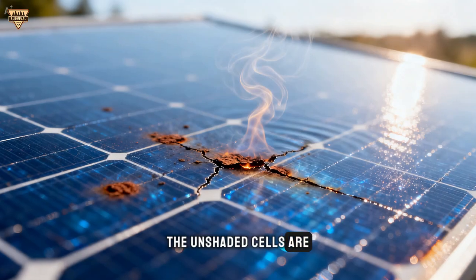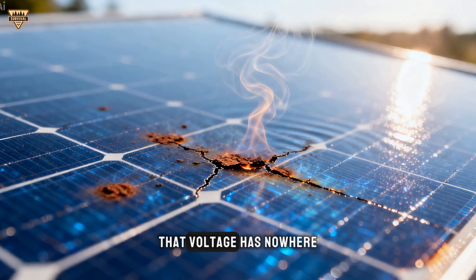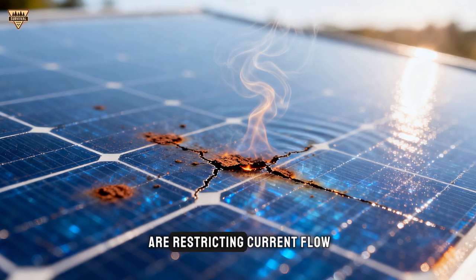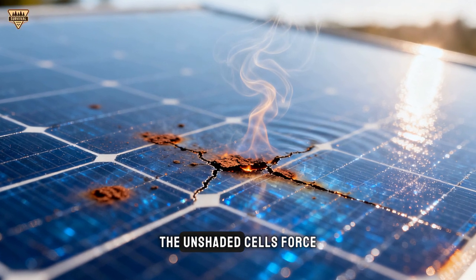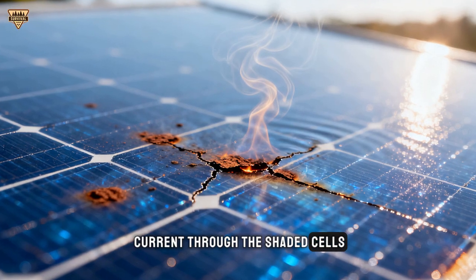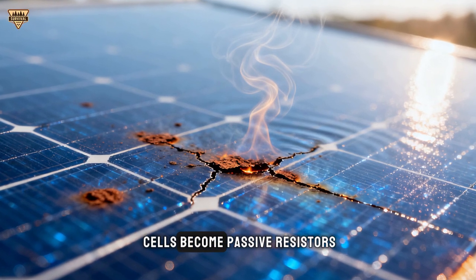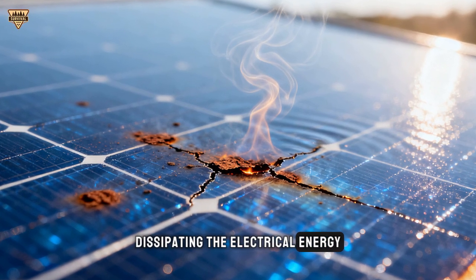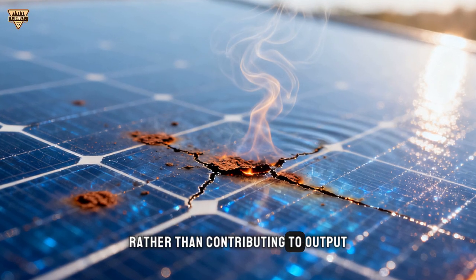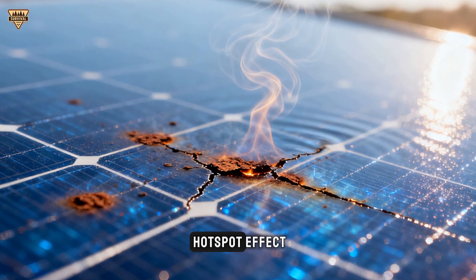The unshaded cells are still generating voltage. That voltage has nowhere to go because the shaded cells are restricting current flow. The unshaded cells force current through the shaded cells in reverse. The shaded cells become passive resistors, dissipating the electrical energy as heat rather than contributing to output. This is called the hotspot effect.